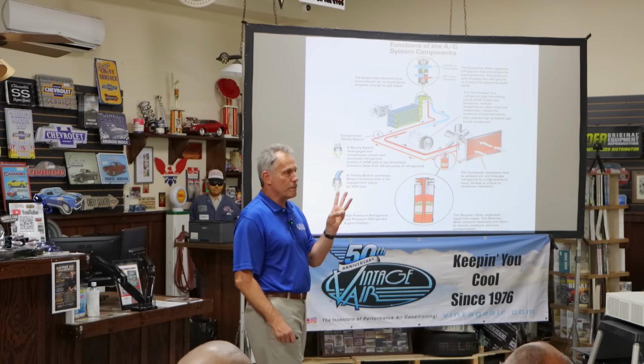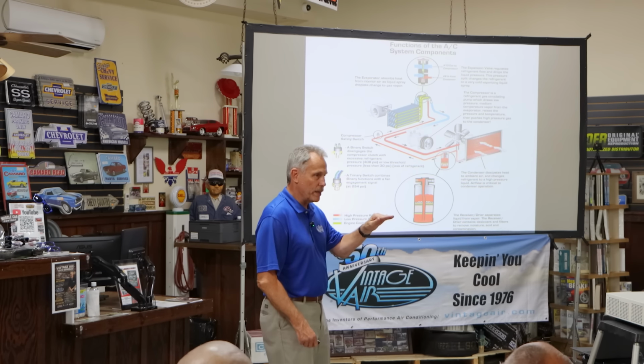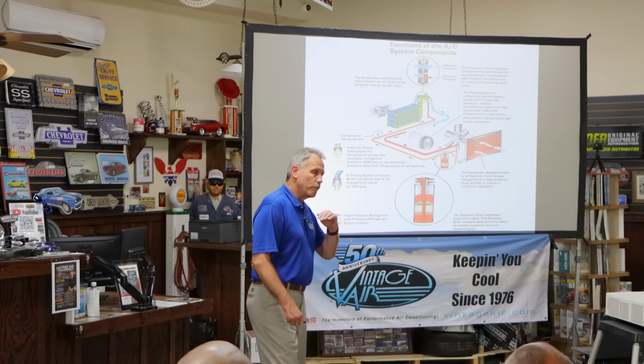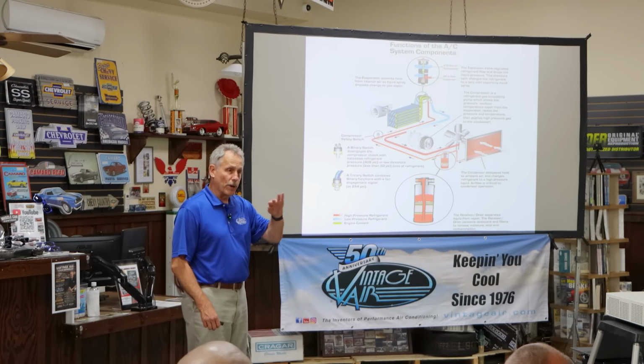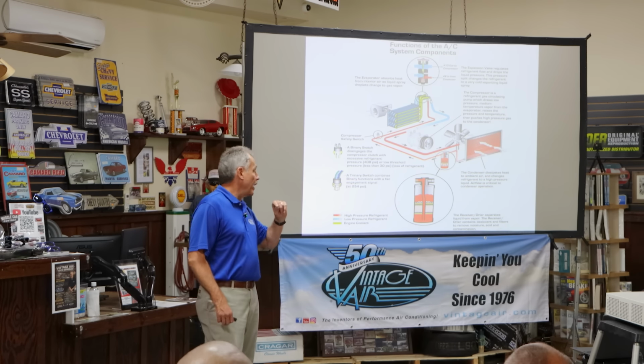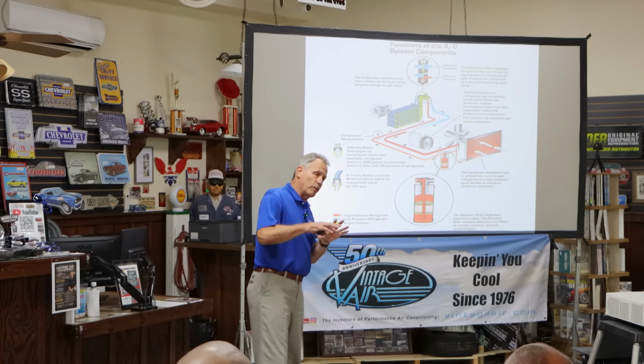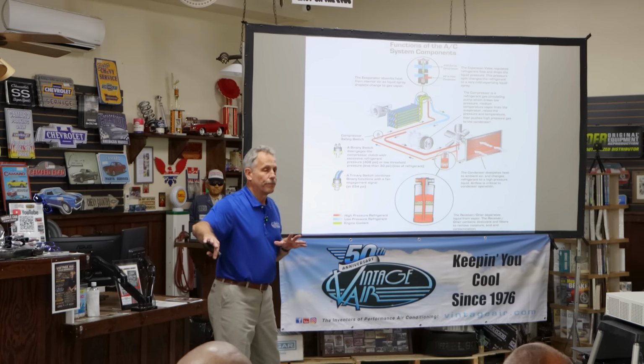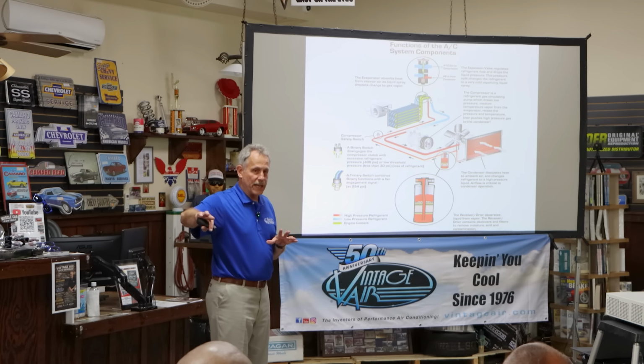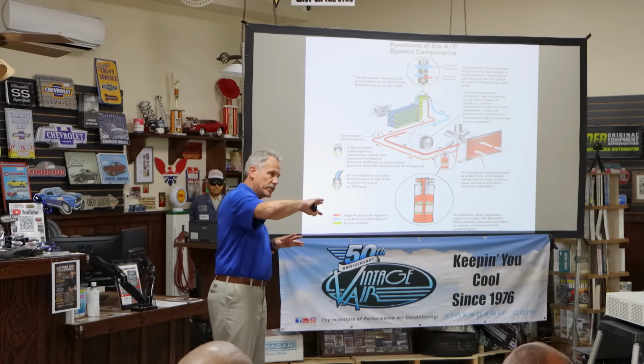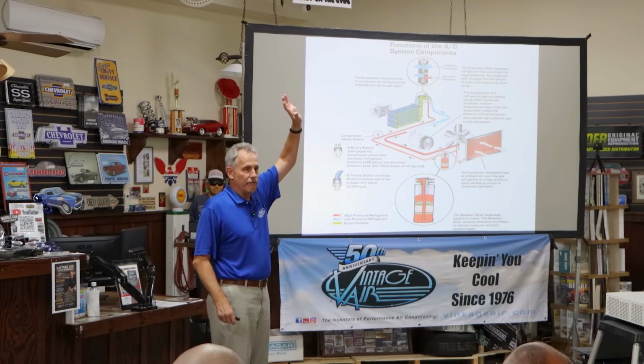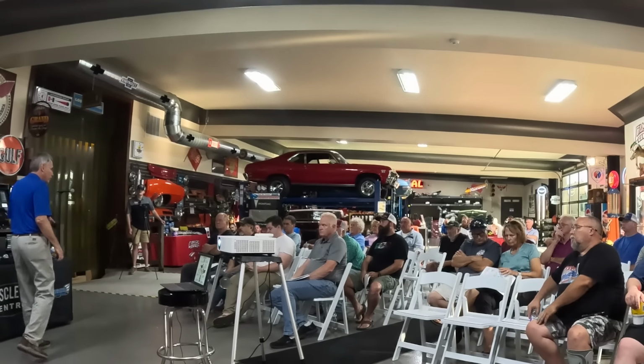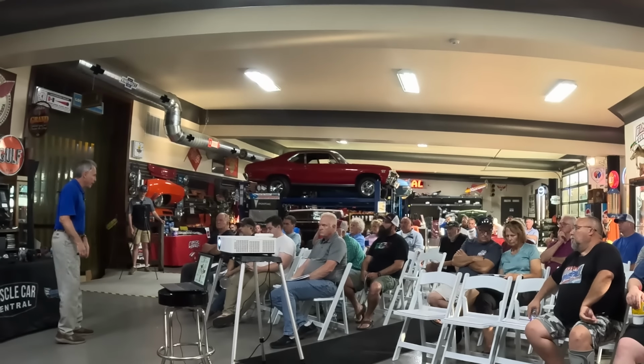Below 30 psi, the compressor can't be engaged. Above 408, the compressor gets disengaged. And the third function, there's a separate part of that switch that at 254 psi sends a signal saying the pressure's high, the fan needs to go on, engaging the fan.